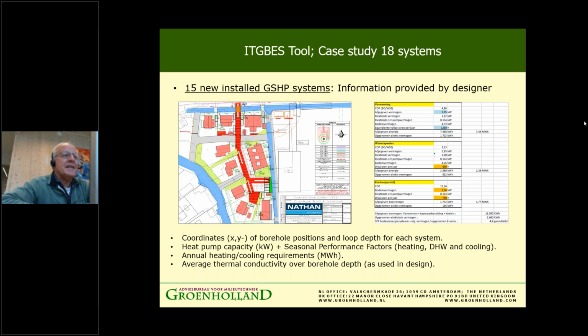This case study shows how the tool works in practice. It covers a total of 18 systems, of which 15 are newly installed, shown on the map on the left in pinkish buildings. The data is provided by the designers: the X and Y positions of the boreholes, loop depth for each system, heat pump capacity, seasonal performance factors for heating, domestic hot water, and cooling, annual heating and cooling requirements, and average thermal conductivity over borehole depth as used in the design. This is standard information you would already have when doing a design.